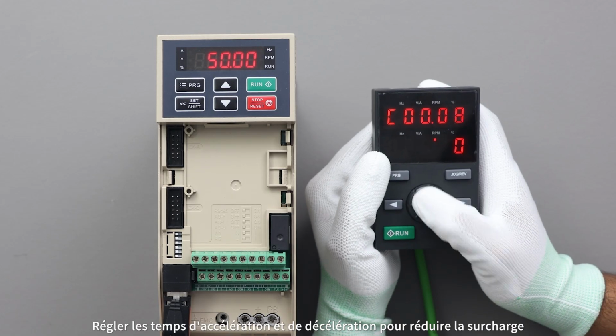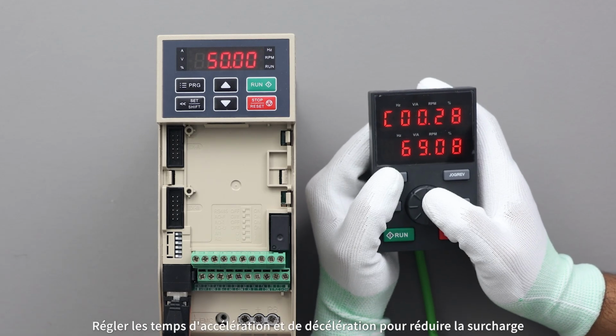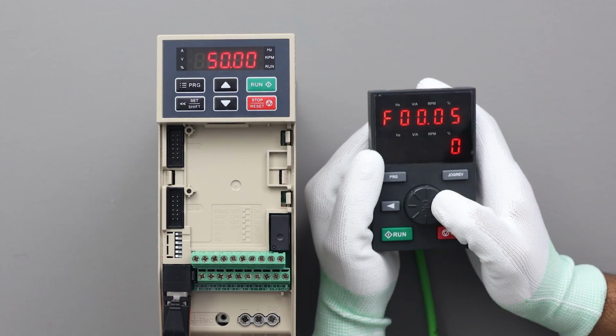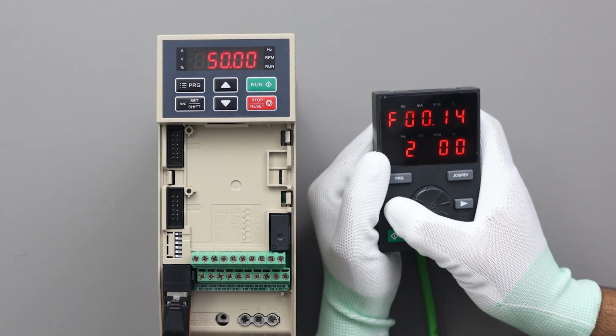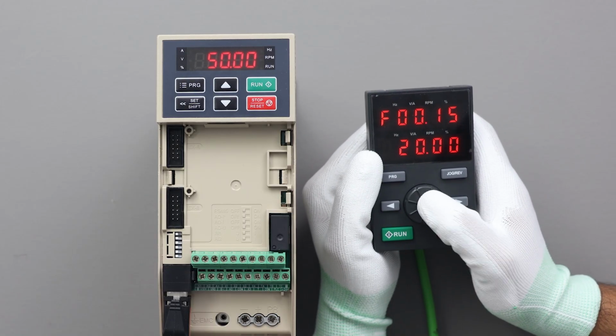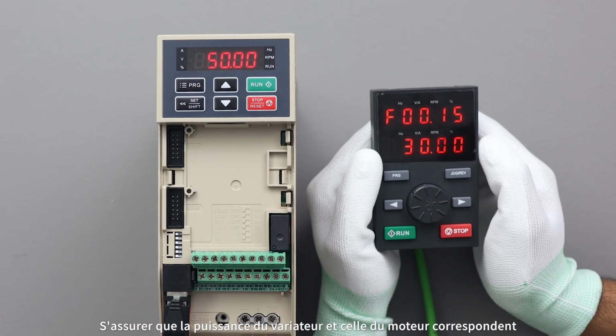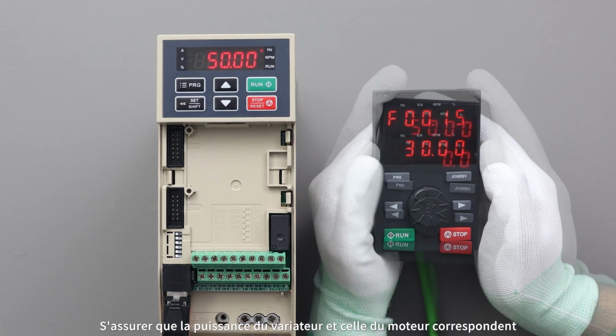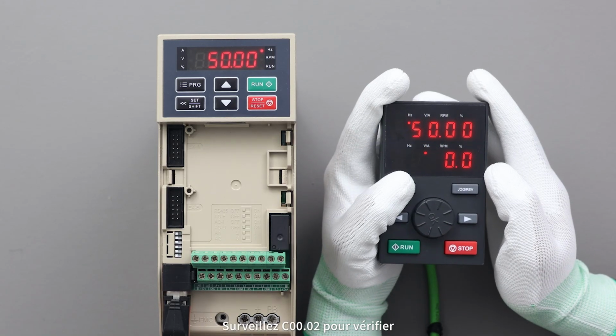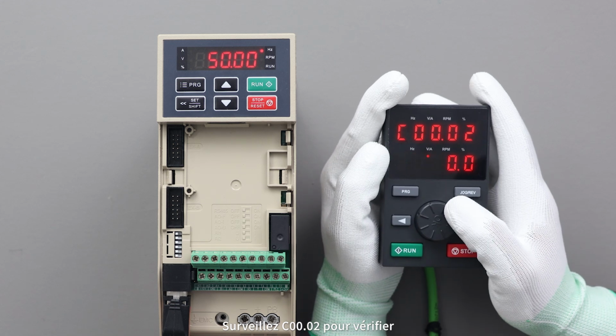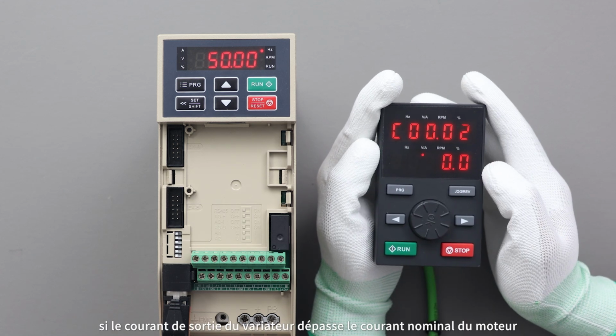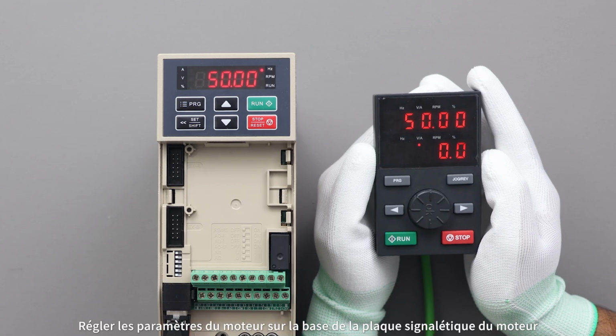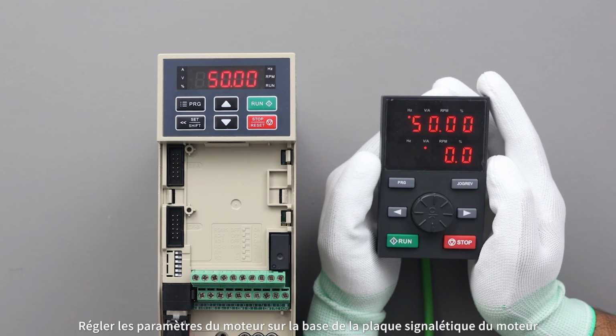Adjust both acceleration and deceleration times to reduce overload. Ensure inverter and motor power match. Monitor C00.02 to check if the inverter's output current exceeds the motor's rated current. Motor parameter settings. Set motor parameters based on the motor nameplate.